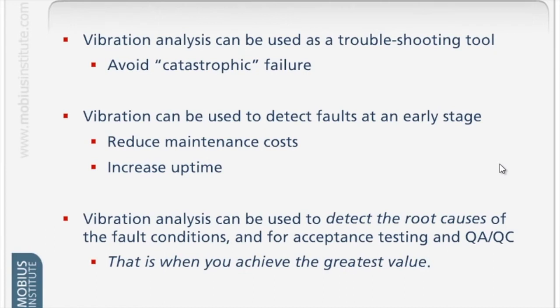All of that is important, but you can do so much more, because if we detect those root causes like unbalance, misalignment, lubrication problems, and soft foot and so on, if we detect those early and correct them, then the bearings probably won't fail. And depending on your industry, we might improve quality, we may reduce energy consumption and all those things if we eliminate those root causes. But whereas vibration can be used to detect the root causes, we can go even a step further and say, let's use vibration to try and prevent the root causes.